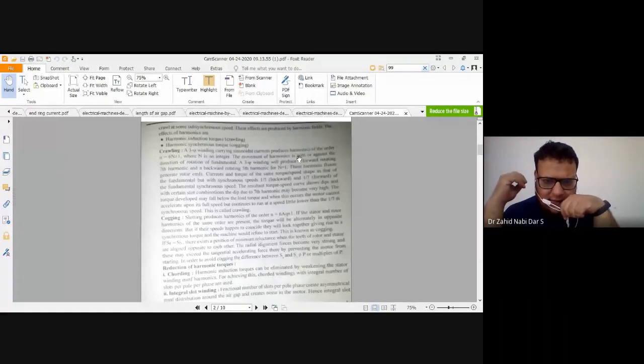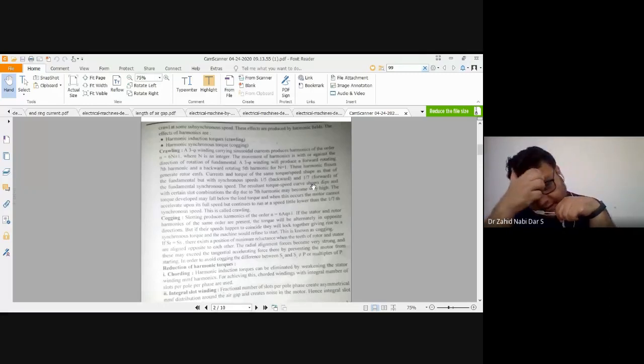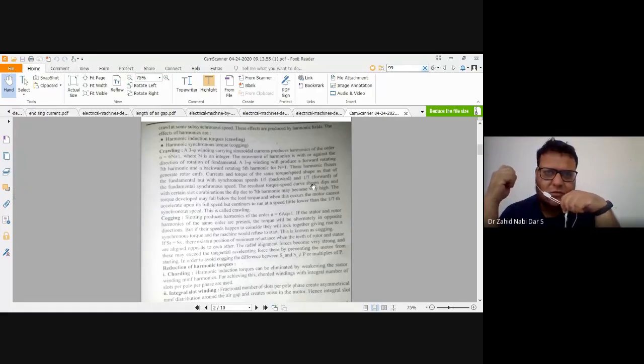Okay, so now the movement of harmonics is with or against the direction of rotation of the fundamental. Usually you have a frequency in any machine, and that is your fundamental frequency, which in India is 50 hertz. Now the harmonic frequencies, taking the odd harmonic components, would be 3f, 5f, 7f. Here, with 6n plus or minus 1, your frequency would be either 7f or 5f. Deviation from the fundamental frequency leads to harmonics, and at these higher frequencies you will get ripples also. The rating of that equipment increases.